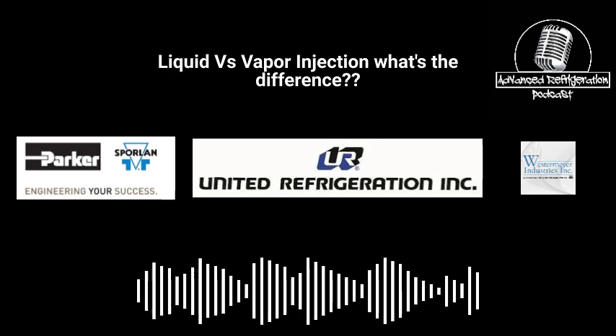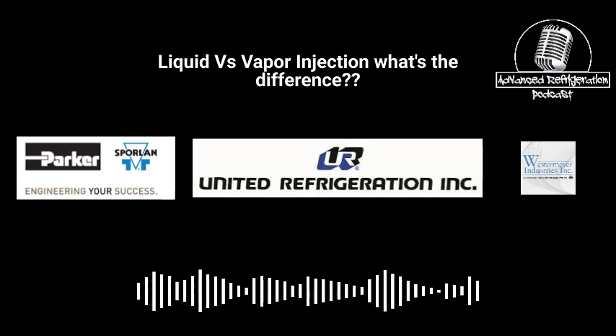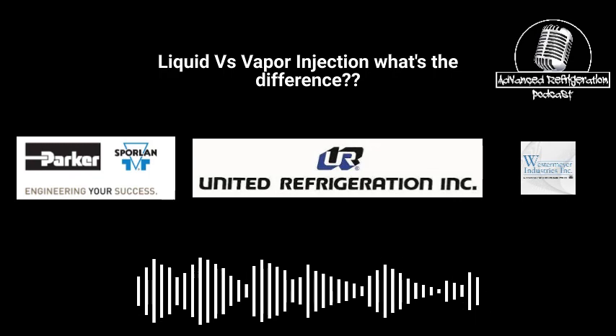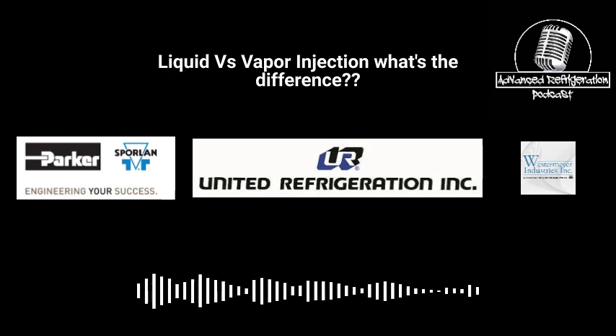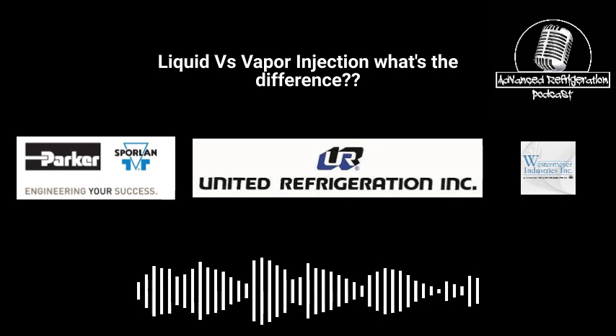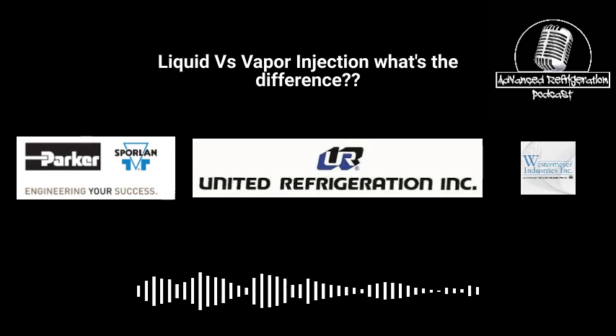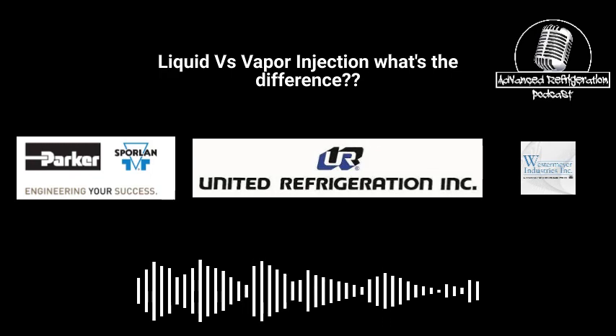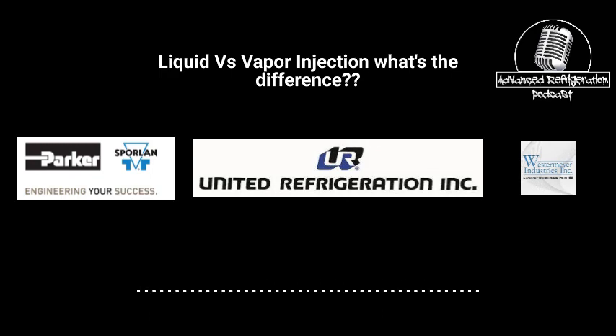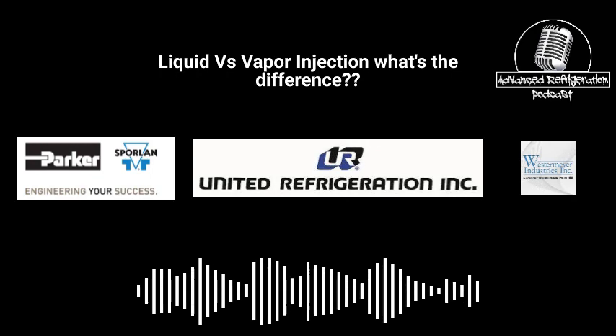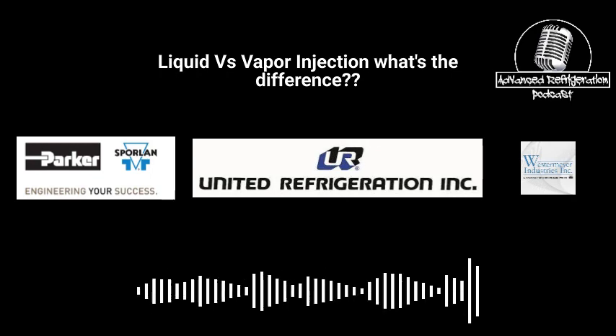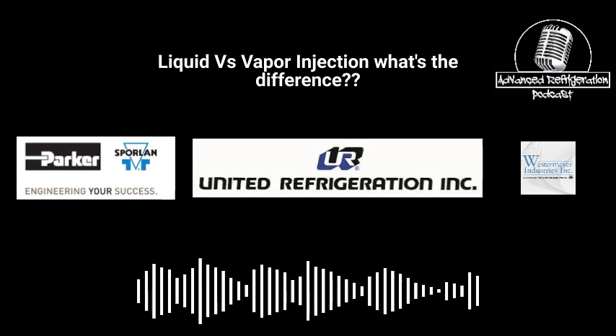Oh yeah. Wow. I don't like to admit this, but I changed out a controller because no matter what I did, I was getting the wrong voltage coming back from the pressure transducer. I did all that math. I'm like, why is this reading wrong? Why is this reading wrong? And I put the new controller in, and as I'm going through all the settings, I'm like, shit. That truck stop part. Almost saved your ass part. Well, that's what it was used for after that.